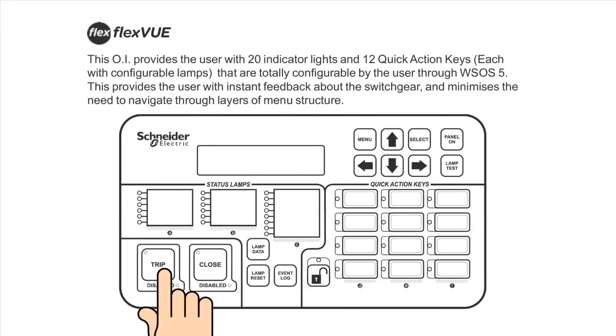Trip key trips the switchgear to lockout, and the green lamp located inside the button indicates the open state of the recloser. Lamp reset key resets the status lamps. Lamps requiring further attention from the operator remain lit. Note that some of the status lamps, such as controller power and terminal live, are continuously updated and therefore not affected by the reset command. Event log key displays the switchgear and controller event log on the LCD display.